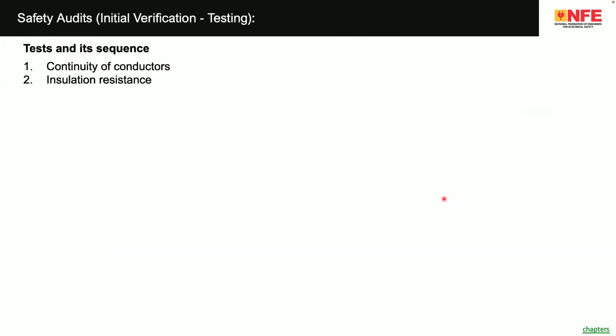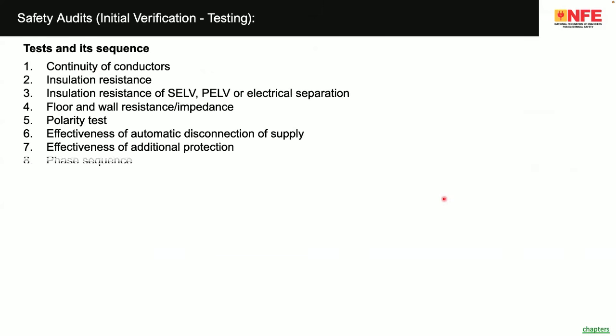After inspection, there is a sequence of subjects to be tested. Starting with continuity of conductors, meaning find out if any loose contacts are there, and that the resistance of the wires after installation is intact. The second one, insulation resistance: test all the insulation resistance of the entire installation, including the panel boards, wires, and so on.